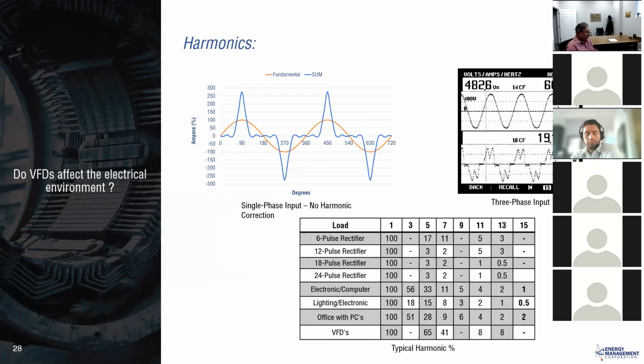If we have a single phase input, this is how the harmonics look. But if we have a 3-phase input for the VFD, this is how it looks. The high current peaks that you're seeing are the result of the capacitor charging on the DC link of the VFD. We have to note that the diodes allow the DC bus capacitor to charge whenever the voltage on the incoming sine wave exceeds the voltage on the DC bus. Thus, we get a large surge in current, and that's what you see here as a current peak.